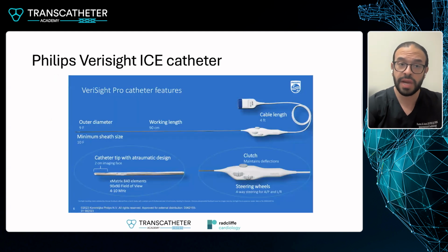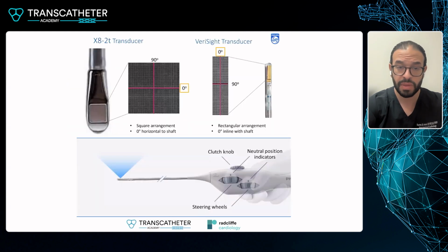In terms of imaging, and specifically the ICE catheter, this is the Philips VeriSight Pro catheter. It is a 9 French outer diameter that will utilize a 10 French sheath with a working length of 90 centimeters. It does have a catheter tip that is quite atraumatic and has 2 steering wheels that allow the operator to steer in an anterior, posterior, or left and right direction, with a clutch in order to maintain grip and maintain those deflections. The differences between an ICE catheter and a TEE catheter are highlighted in the slide.